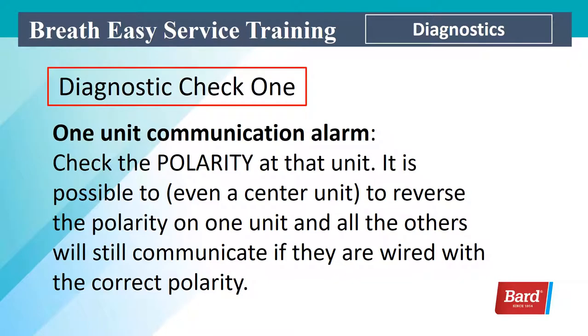If you have one single unit showing a communication alarm, check the polarity at that unit. It is possible, even if it's a center unit, to have reversed polarity on just one unit while all the others still communicate, provided they are wired with the correct polarity.